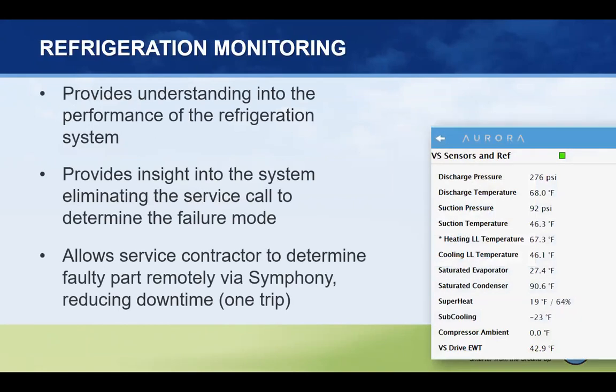It provides us an understanding of the performance within the system. It eliminates a service call to determine what the failure mode is, and it allows the service contractor to determine a faulty part remotely. And as you can see on the right, the view of what it gives you is discharge pressure, temperature, suction pressure and temperature, and the liquid line temperatures in both modes. And then it calculates for you your saturated evaporator and condenser based on the refrigerant in the system, tells you superheat, subcooling, and then even the drive temperature that you have on the system.